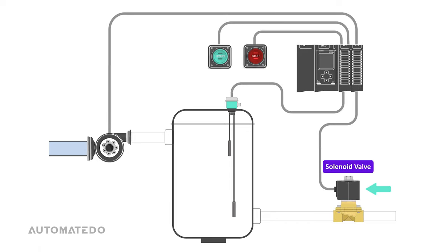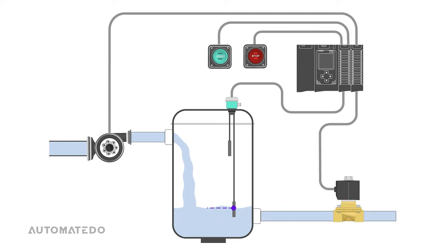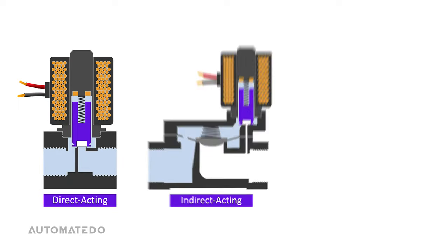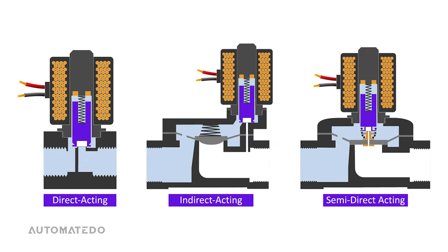Finally, we look at an industrial application where the solenoid valve controls the liquid level in a tank. When the start button is pressed, the pump motor turns on and fills the tank. When liquid reaches the first probe, the conductivity level sensor sends a low level signal to the PLC, which closes the solenoid valve. When liquid reaches the second probe, the PLC receives a high level signal, turns off the pump, and opens the solenoid valve to let the tank level fall.